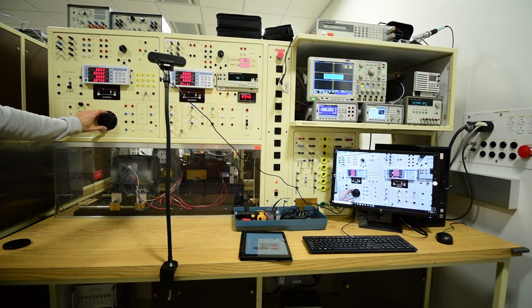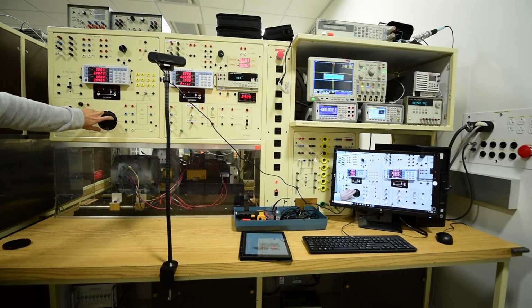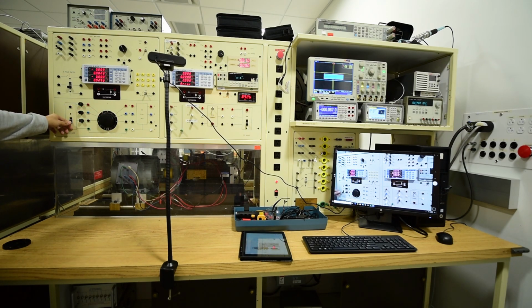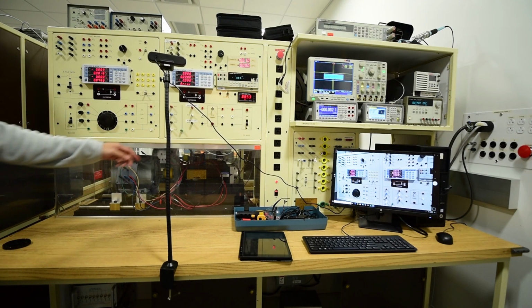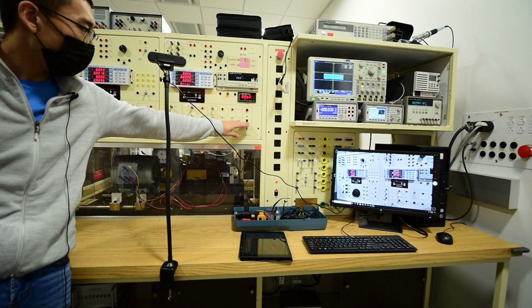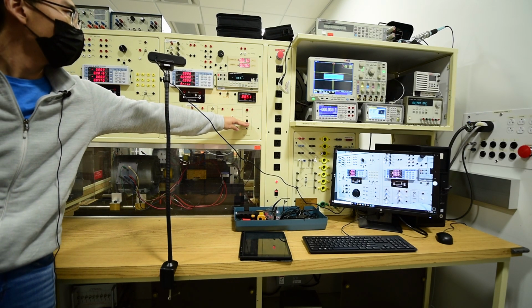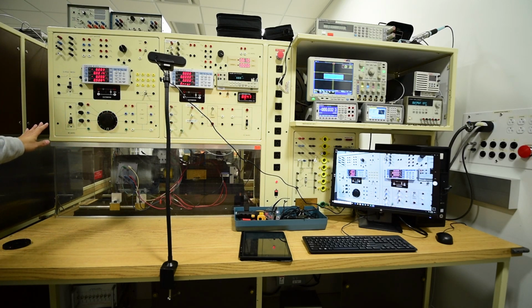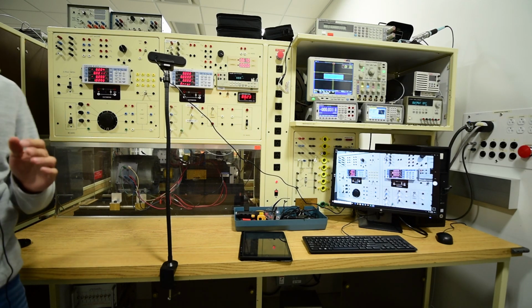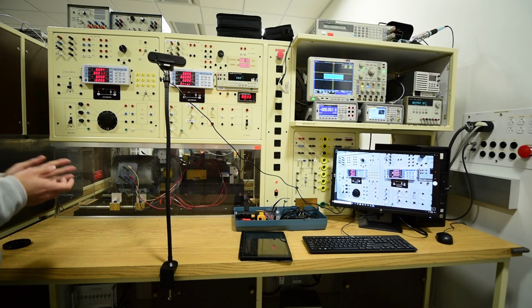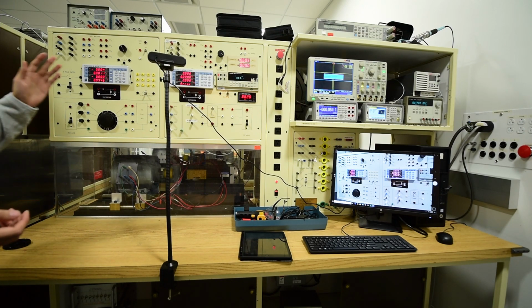That means twisting this knob counterclockwise all the way to 0, and this switch is off. You also want to make sure the dyno control is off and the DC mains is off. If these switches are off, all of the terminals will be powered off, so now it's safe to do any connection. Remember, do not change any connections when any of these switches is on.